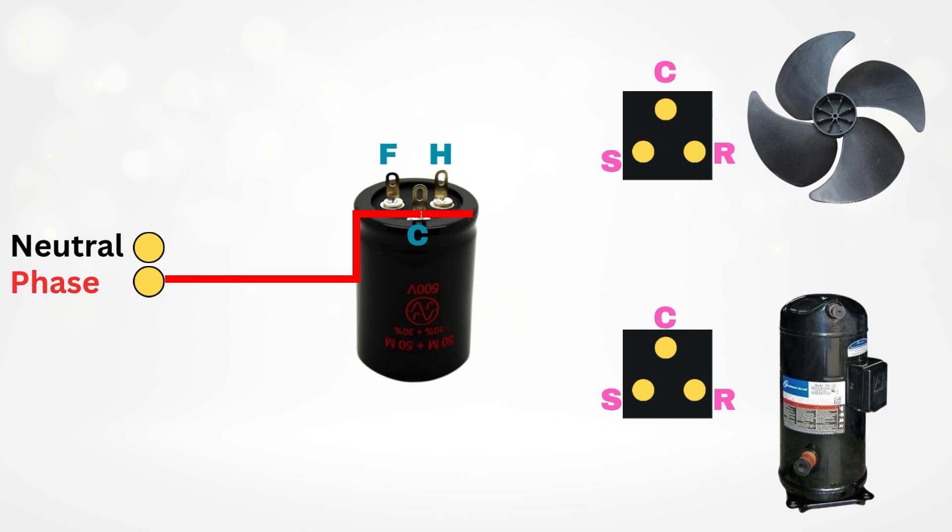Next, from the common C terminal you run two wires. One goes to the running terminal of the compressor. The other goes to the running terminal of the fan motor.